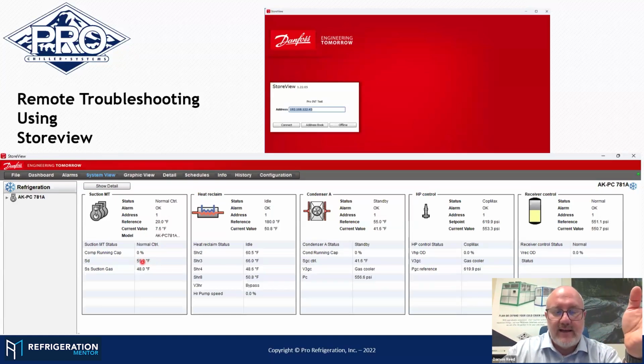My discharge, I can see what my discharge temp is, and I can see what my suction gas temp is. Perfect. That compressor is just holding in a standby condition. Same with the heat recovery. I get that view, and I can see I'm idle. That's because my compressors aren't running. Why would I be operating heat recovery if my compressors aren't doing anything? So status is okay. I've got a reference value of 180 and a current value, so we monitor a remote sensor. When that compressor starts, if I'm sitting here watching it, I expect this to go into heat recovery mode because I'm 130 degrees below my reference point, right? The fact that it's that low, and knowing this particular customer, they just have hours and hours of downtime where they're not in operation. So I know that's their status.